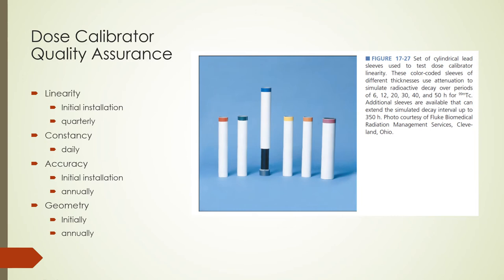At least one sealed source, usually cobalt-57, is assayed, and its measured activity, corrected for decay, must not differ from its measured activity on the date of the last constancy test by more than 10%. The test for accuracy is done at initial installation and annually thereafter, by assaying two or more sealed radioactive sources whose activities are known within 5%. Often cobalt-57 and cesium-137 are the two sources used, and the measured activities must be within 10% of the actual activities. Geometry tests the response of the dose calibrator to different size samples and different sample volumes. If volume effects affect measurements by more than 10%, correction factors must be determined. It is done at initial installation and annually or any time the dose calibrator is moved.